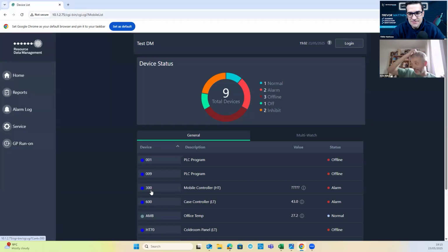So that's, I think, a pretty good demonstration with RDM of how robust it is with old controllers. My data manager is about 18 months old. The controller I've just connected is well over 10 years old. And all I've done is put an address in it, connected it on, and it's appeared. So that is the beauty of using these. There's no type files, like you get with some manufacturers where you're going, oh my God, that's a really old controller or a really new controller, where's my type file for it? It'll go straight on. So that's a miracle. I'm quite pleased that's come up.